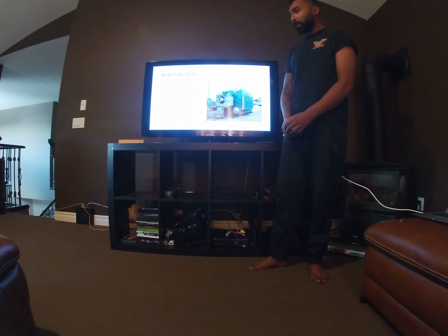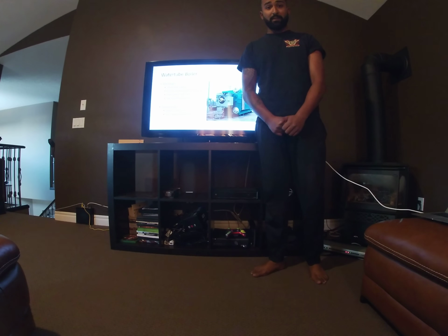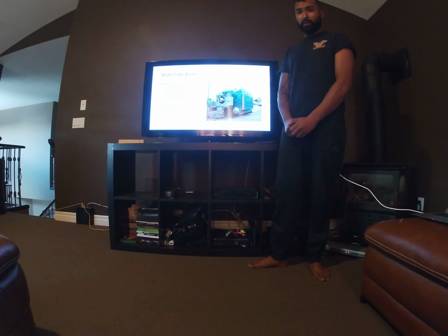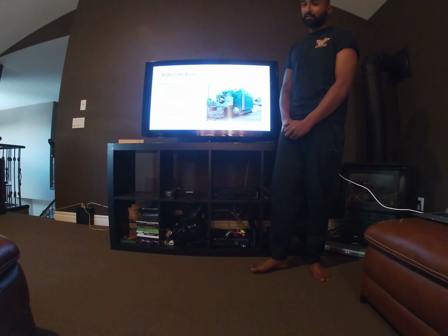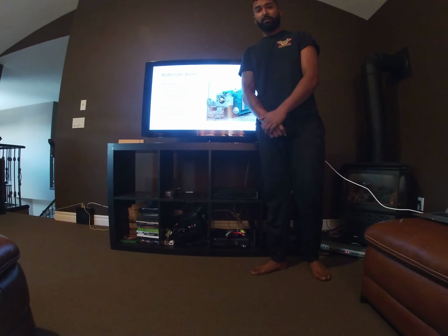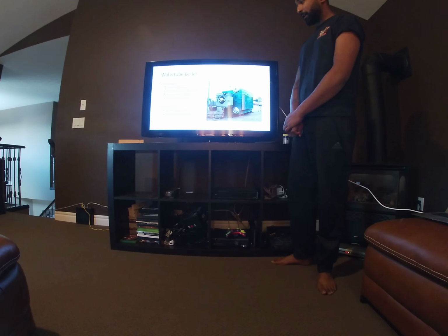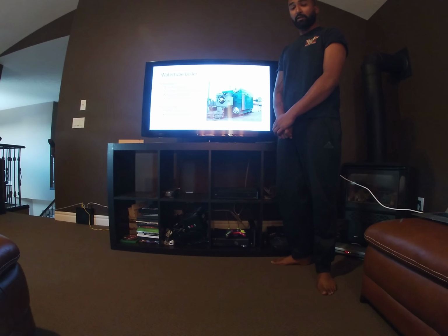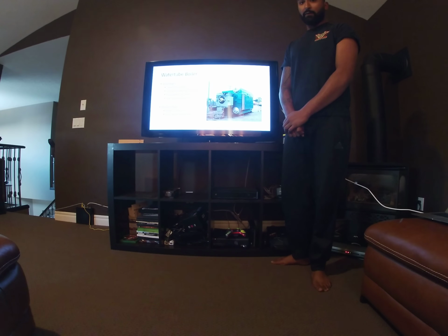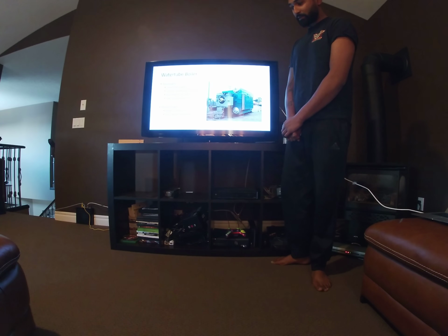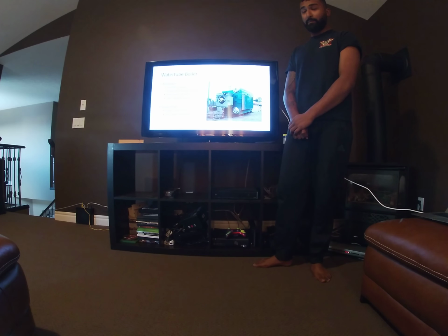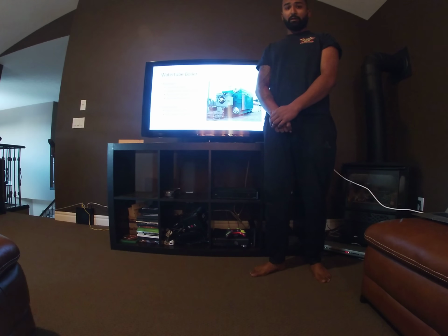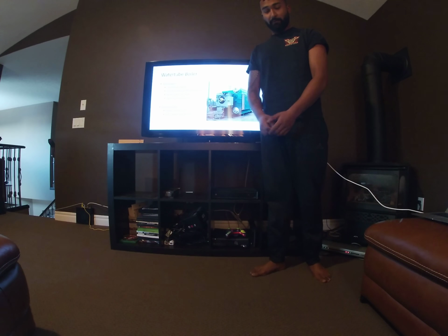in the shell. They have a low maintenance cost. They're very easy to take care of. A disadvantage of the water tube boiler would be a higher initial cost, and they're very strict on water treatment. If you're not strict on the water treatment, calcium deposits will form within the tubes that cause hot spots in the tubes, which could cause tube failure, which is very dangerous.